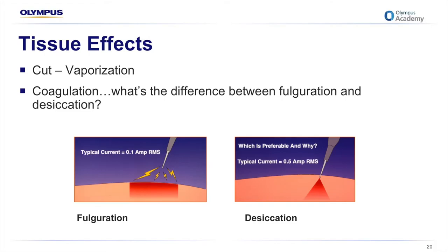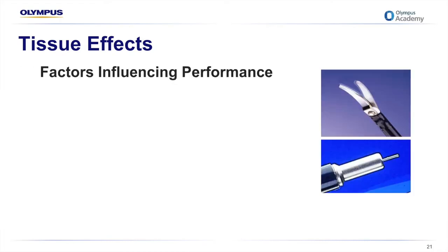In doing so, touching the tissue reduces the current concentration, resulting in less heat being generated. This form of energy works well to stop bleeding. You'll see a few important factors here that influence the cutting performance of electrosurgical instruments. The type, as well as the size of the electrode tip, influences the ability to cut. A smaller electrode means higher current density. In other words, a fine edge or point on the electrode will require less power to yield a clean cut.